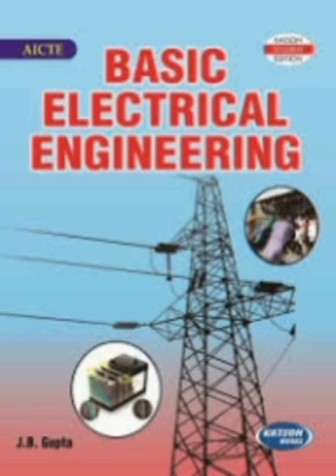A three winding transformer can be used to interconnect power systems at different voltage levels. The tertiary winding is used as a supporting winding in a Y-Y transformer to stabilize the neutral and to avoid third harmonics. Application of different connections: delta-delta. This connection is used where we have simple 3-phase load, especially at low voltage level. No mixed loading is possible.